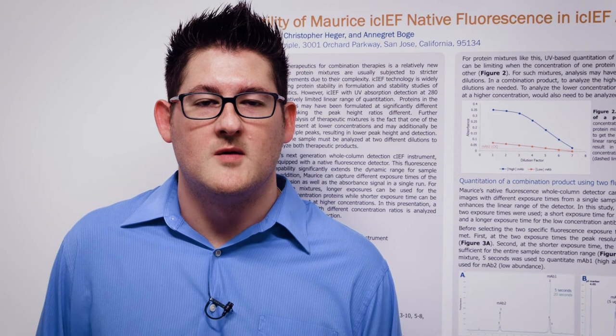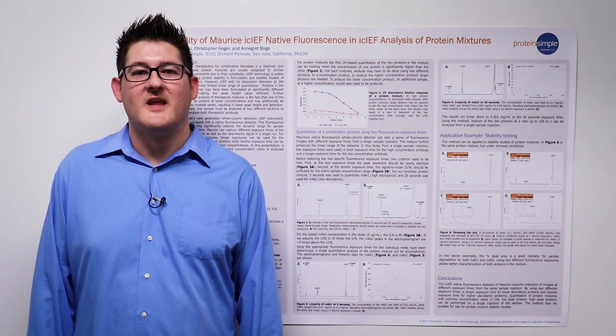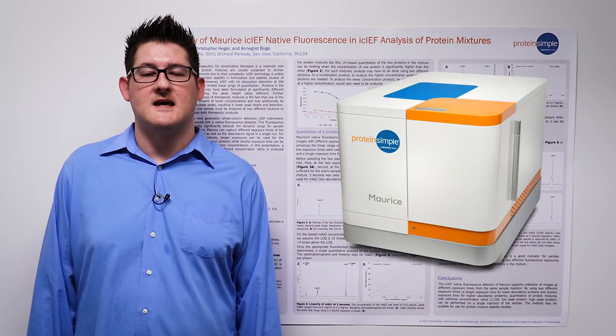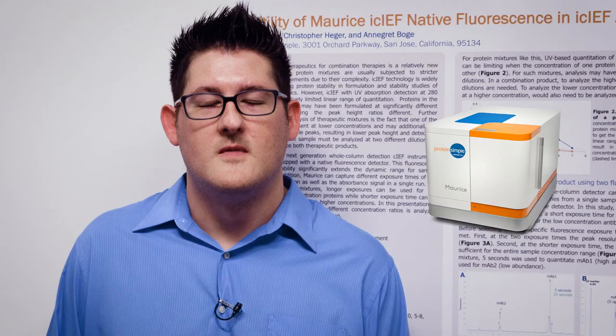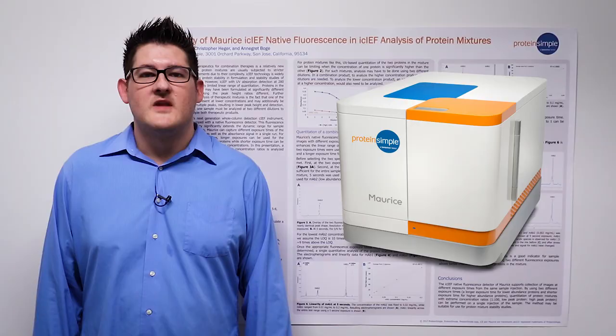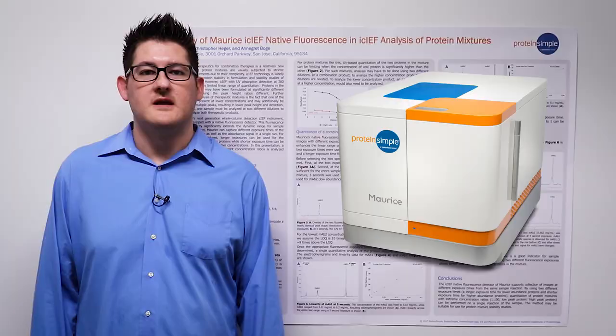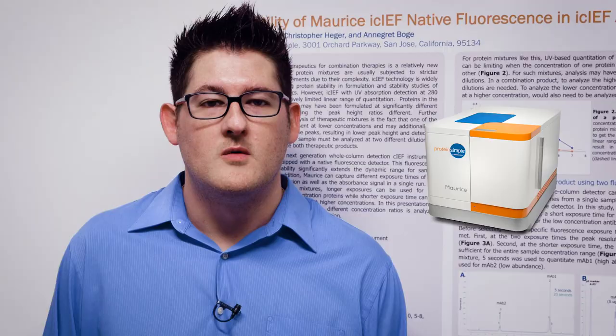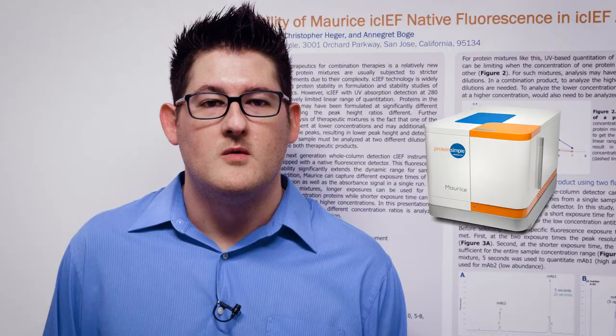We show that complex samples containing more than one protein at different concentrations can be accurately and reproducibly quantitated on Maurice, eliminating the need for sample dilution. The Maurice system innovates conventional CE technology by combining cIEF and CE-SDS into a fully automated platform, enabling protein analysis by either size or charge. Our unique ICIEF technology is augmented by a sensitive native fluorescence capability, which increases your dynamic range and improves sensitivity over conventional UV-based detection methods. For more information, please visit the Maurice webpage. Thank you.